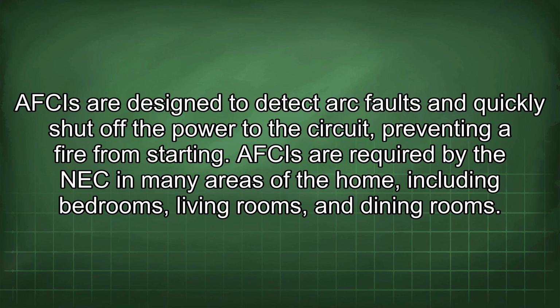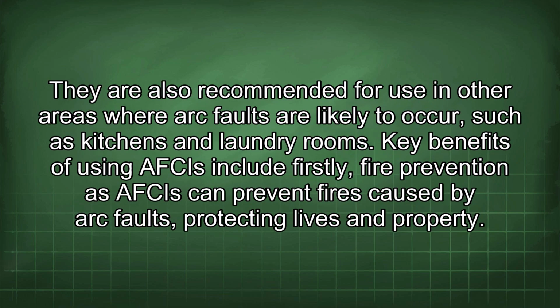from starting. AFCIs are required by the NEC in many areas of the home, including bedrooms, living rooms, and dining rooms. They are also recommended for use in other areas where arc faults are likely to occur, such as kitchens and laundry rooms. Key benefits of using AFCIs include, firstly, fire prevention, as AFCIs can prevent fires caused by arc faults, protecting lives and property.